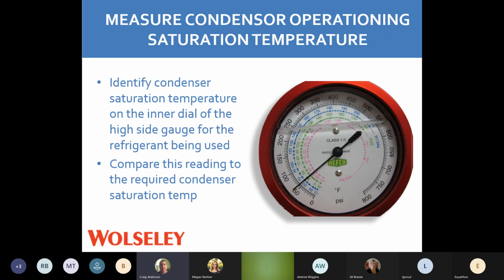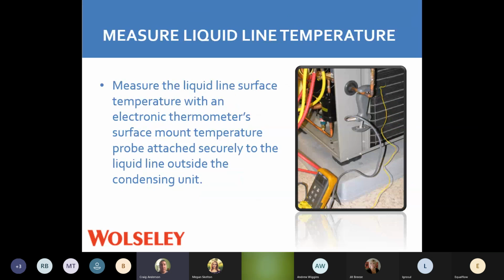Same thing. Now we're looking at our high side gauge, our red gauge. So we're on the small line, the 3/8 line, the high side. Same application. We're going to check the readings. We're going to see what that high side's doing. And we're going to check the temperature of that high side copper that's going through. Same application we did with the suction line. We're doing it with the other line.